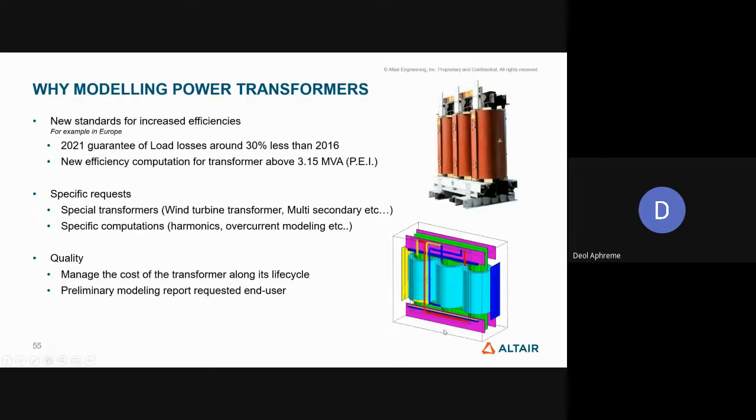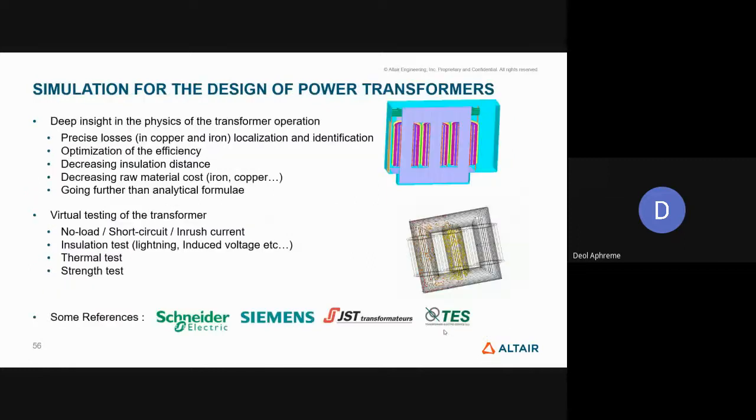And then, yes, overcurrent and harmonics, to understand the aging effect on the transformer. All this can be simulated. Then the quality of the material and of the transformer being simulated, which speaks about the life cycle and the aging effect. All this can be simulated, and you can even give real-world test scenarios which directly give you fault conditions. At the end of every user manual we see these fault conditions and appropriate reactions. Most of the time people cannot test these huge power transformers for such fault conditions. That's why we simulate those conditions and give appropriate results.